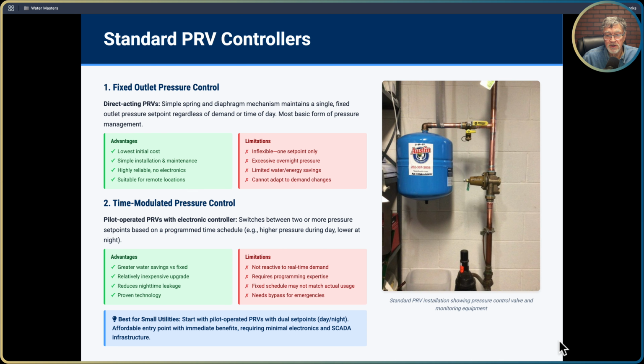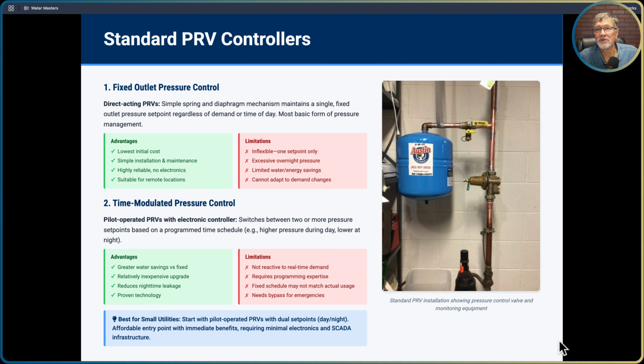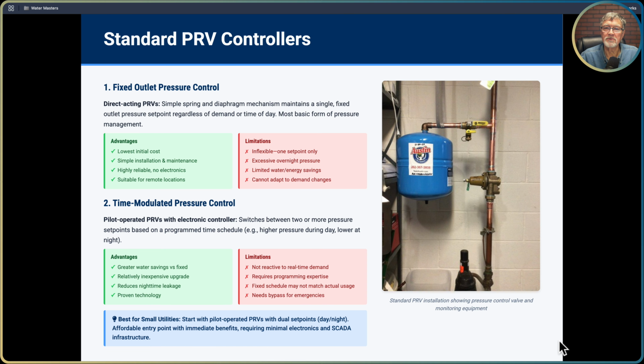Our fixed outlet pressure control is going to be a direct acting PRV. It's a simple spring and diaphragm mechanism that maintains a single fixed outlet pressure set point regardless of demand or time of day. It's really the most basic form of pressure management and also the least expensive. So: lowest initial cost, simple installation and maintenance, and highly reliable. There's no electronics involved, and it's suitable for remote locations because it's a set-and-forget type of thing. The limitations are obviously that it's inflexible, with one set point only. You'll get excessive overnight pressures with this type of system, which is what we're trying to get away from. It has limited water and energy savings, and it cannot adapt to demand changes, obviously.